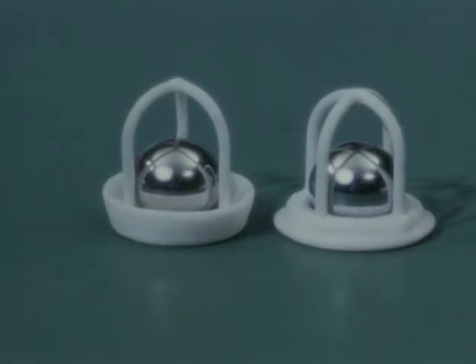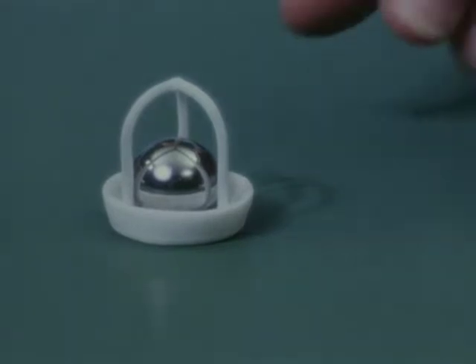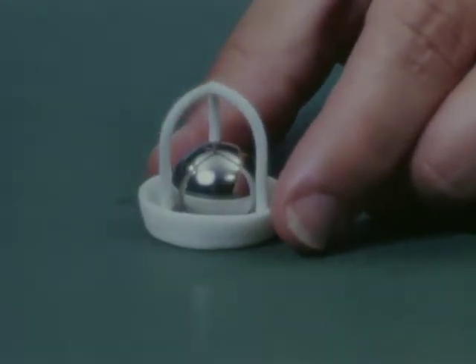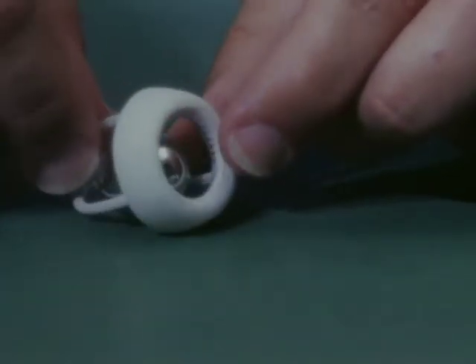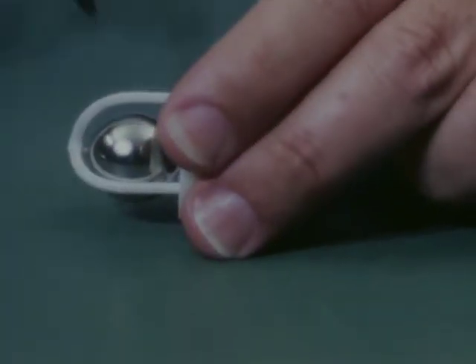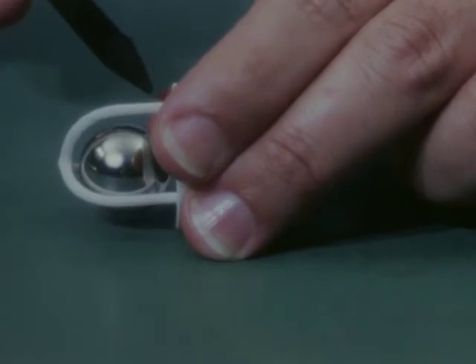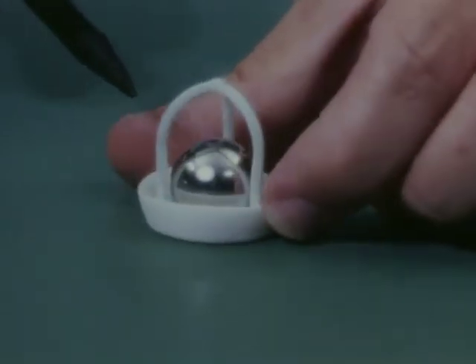This flaw was quickly eliminated and the present 2320 aortic and 6320 mitral prostheses evolved, currently in use in our clinic. They feature a metal poppet, the composite seat, a wide distance between cage and poppet which flares even more near the apex, and a two-ply cloth cover.